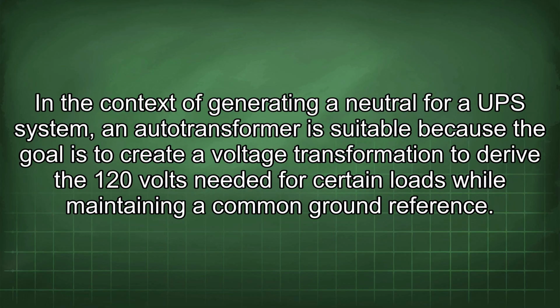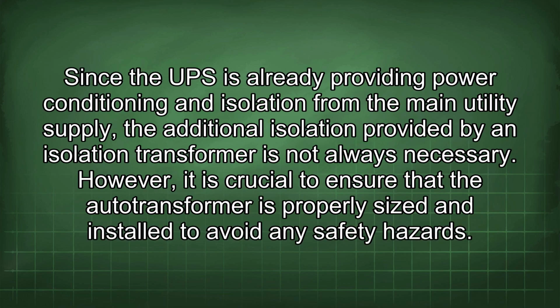Autotransformers are typically smaller and less expensive than isolation transformers, but they do not provide the same level of electrical isolation. In the context of generating a neutral for a UPS system, an autotransformer is suitable because the goal is to create a voltage transformation to derive the 120 volts needed for certain loads while maintaining a common ground reference. Since the UPS is already providing power conditioning and isolation from the main utility supply, the additional isolation provided by an isolation transformer is not always necessary. However, it is crucial to ensure that the autotransformer is properly sized and installed to avoid any safety hazards.